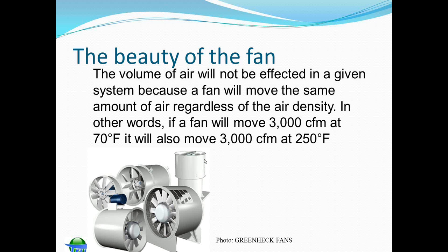We call this 'the beauty of the fan.' A fan actually moves a fixed volume regardless of air density — if it's moving 3,000 CFM at 70°F, it will also move 3,000 CFM at 250°F. Since a fan moves air at a specific volume flow rate independent of density, a vane anemometer can similarly be used to measure airflow independent of air density.